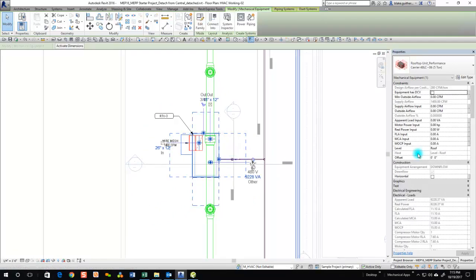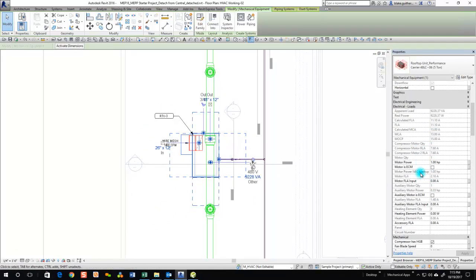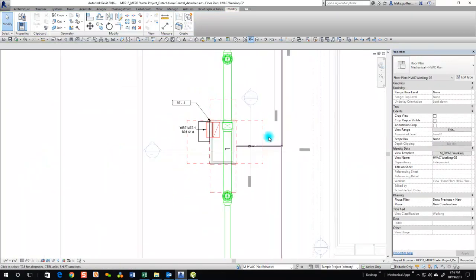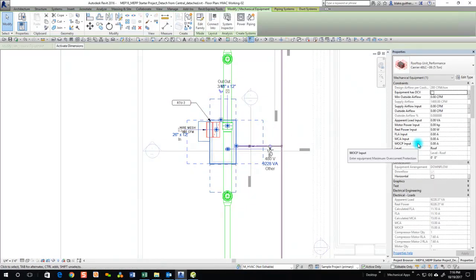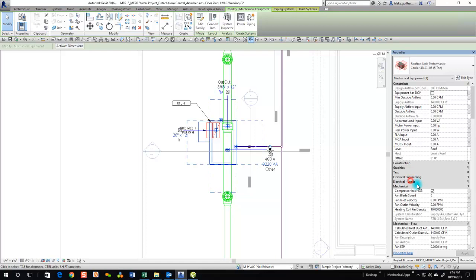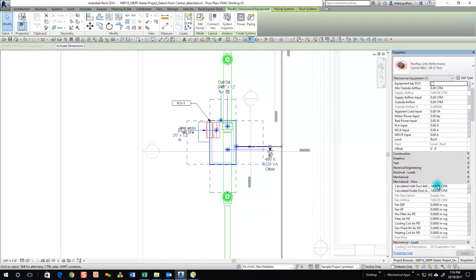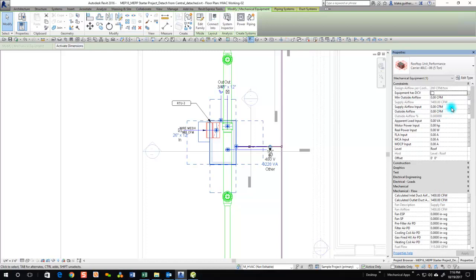So we've already talked about we have full electrical loads for the electrical discipline to begin with, just by placing the unit. We've made our connections to the unit now. So now we're able to see that based upon our connected airflow, we're at 280 CFM per ton. This supply airflow, as discussed previously, is using the connected airflow unless we override that. So we can look at our mechanical flow here. So here's our two connected airflow streams. So we could override this or we could leave it.